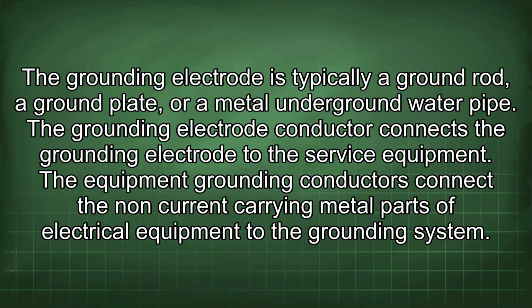The grounding electrode is typically a ground rod, a ground plate, or a metal underground water pipe. The grounding electrode conductor connects the grounding electrode to the service equipment. The equipment grounding conductors connect the non-current carrying metal parts of electrical equipment to the grounding system.